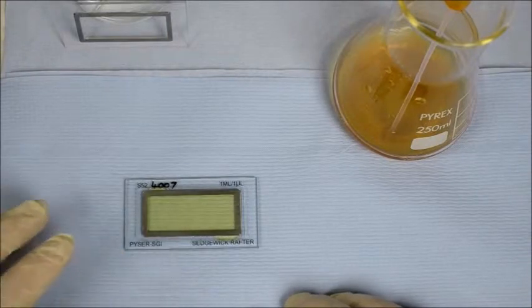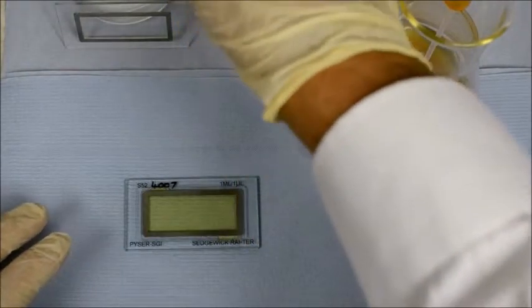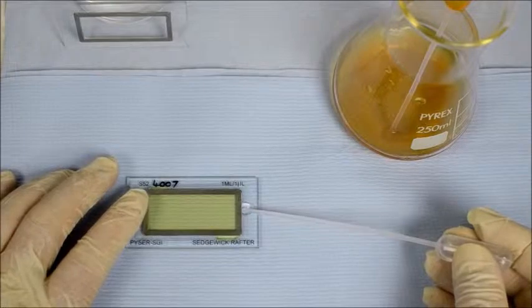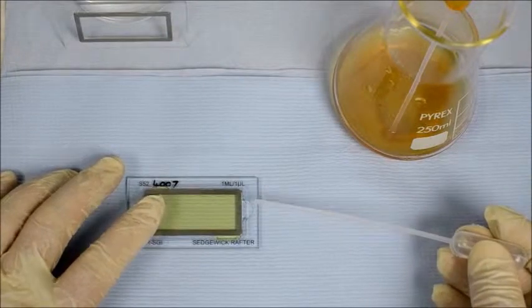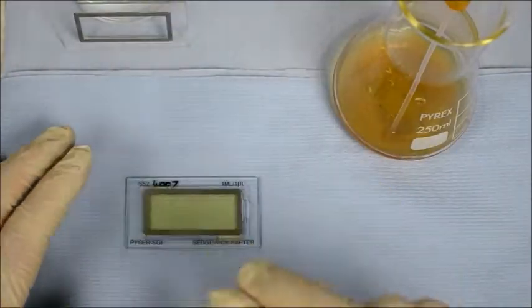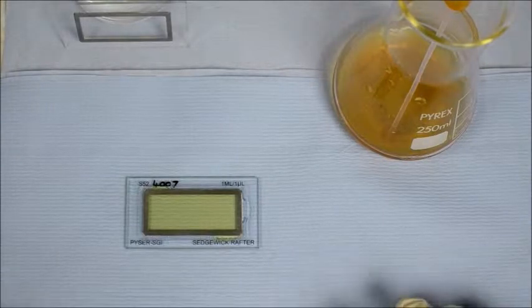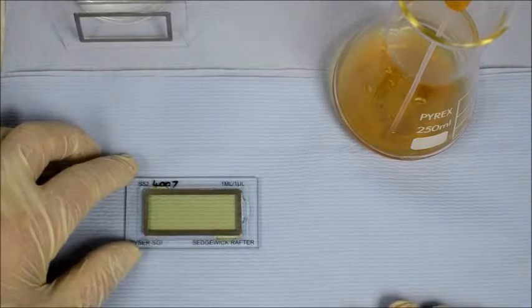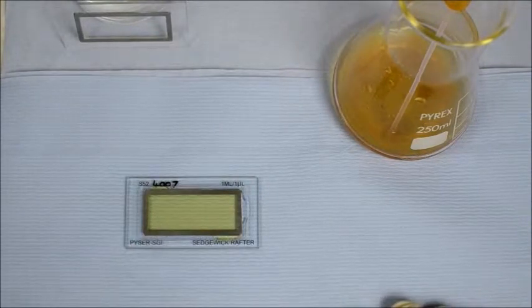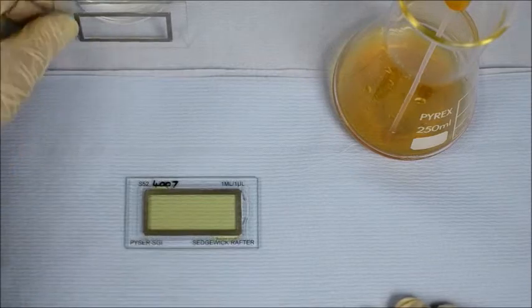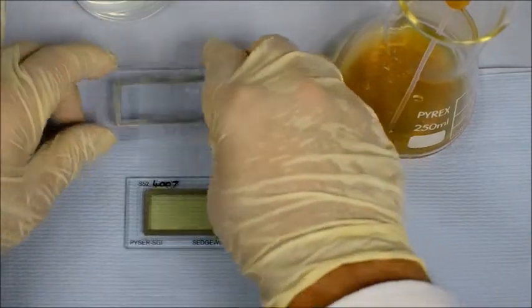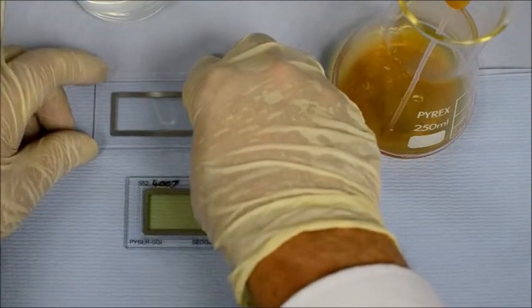So to prevent bubbles forming, if you take a small drop of distilled water and just place it on the edge of the chamber, a small drip against the side wall here like this, then that will prevent bubbles forming during the actual evaporation of the sample away. Now, the base of the Sedgewick Rafter can be plain or gridded. This is a gridded model, and this one here is a plain base model.